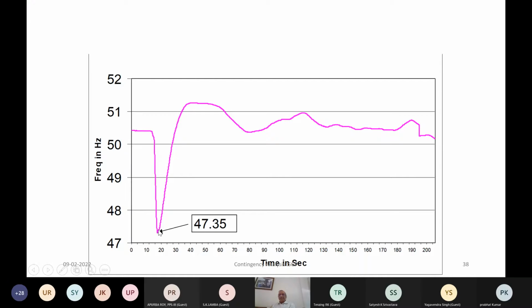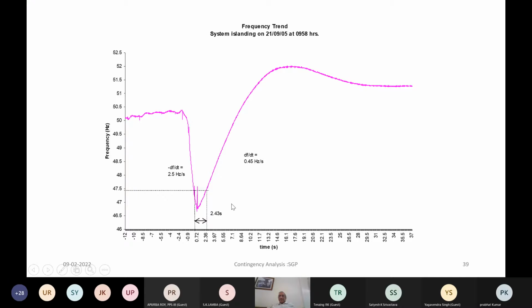Islanding takes place. Once islanding takes place, if there is enough load shedding, then the island will have surplus generation, so frequency will shoot up, and then the governing action will take place to stabilize at a new value. So this is a sort of a curve.